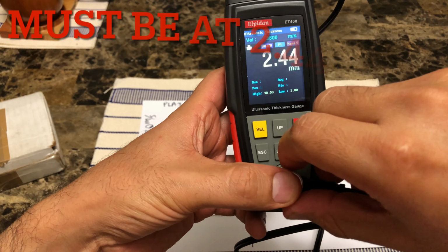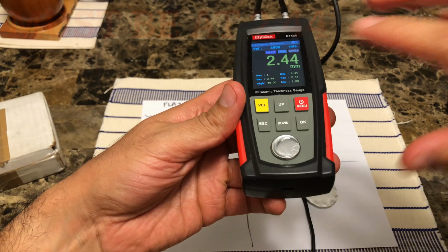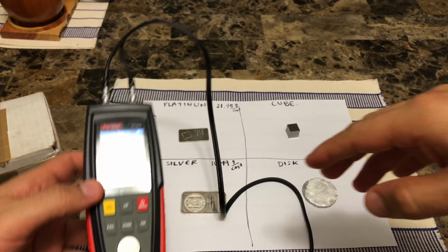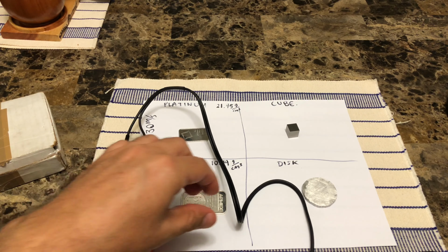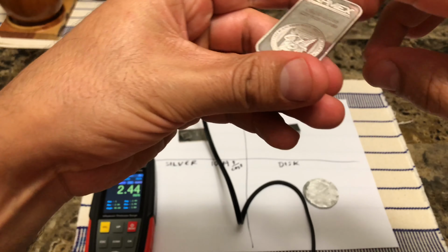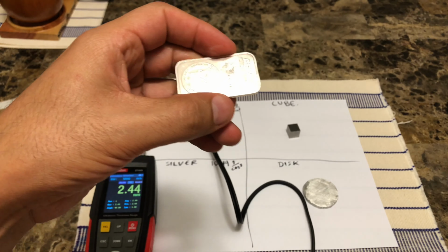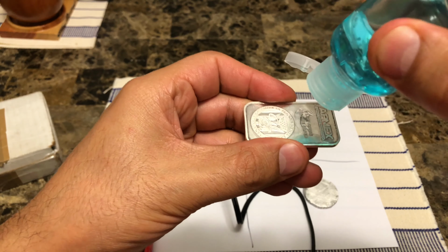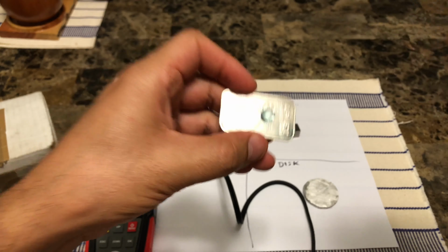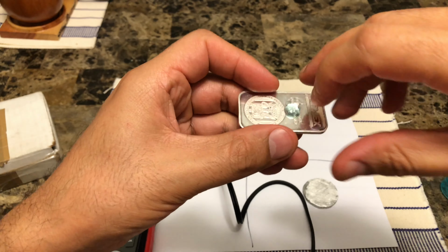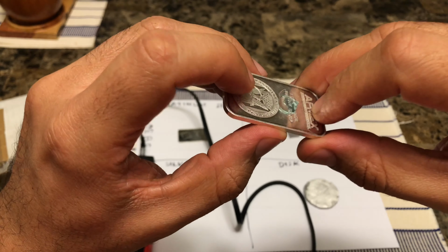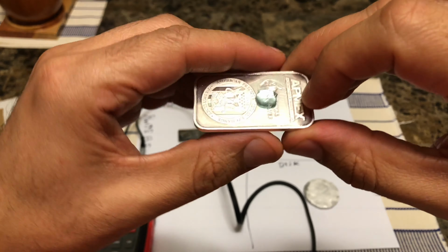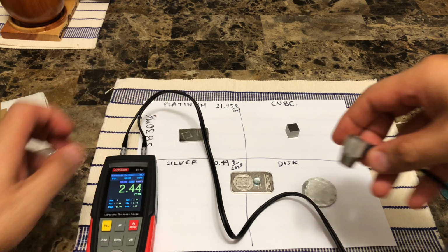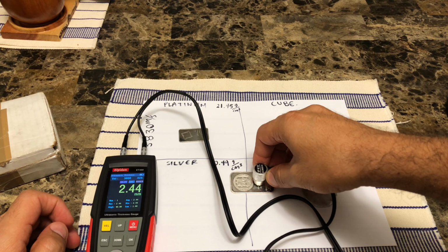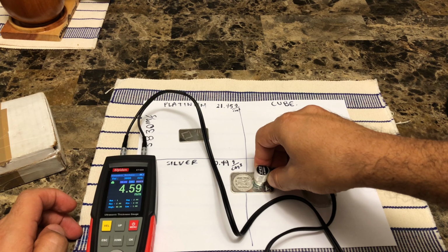So there you have it. It's already been calibrated. Make sure you wipe this off. Now we're gonna measure the thickness of this silver bar. We're gonna put some ultrasound gel on it before we put the probe on. I chose this particular point in between the seal and the writing, and I'm gonna set it down and measure the thickness at that point.